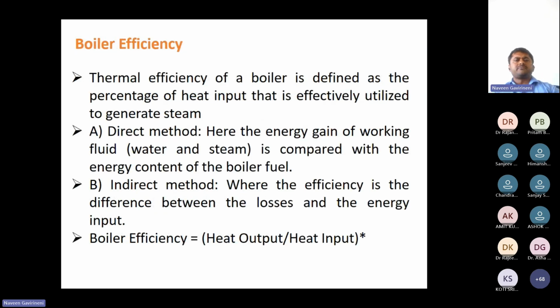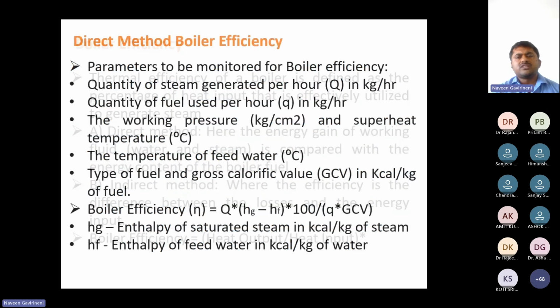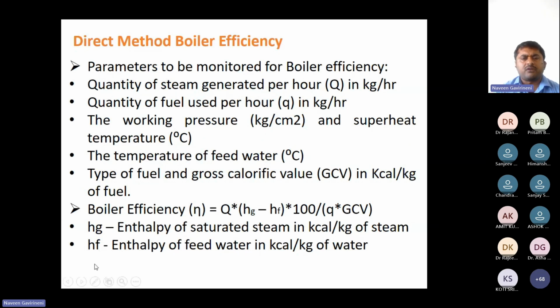So this is the boiler efficiency method. There are two methods: the direct method and the indirect method. This is the direct method, and I am giving the formula here: mass of steam into the enthalpy difference of steam and feed water, by mass of fuel into GCV. Here we are not getting the exhaust efficiency and exhaust losses. There are 9 types of loss, which I will explain in coming slides. Those losses do not come into this. We consider this preliminary efficiency only, not from a detailed point of view.